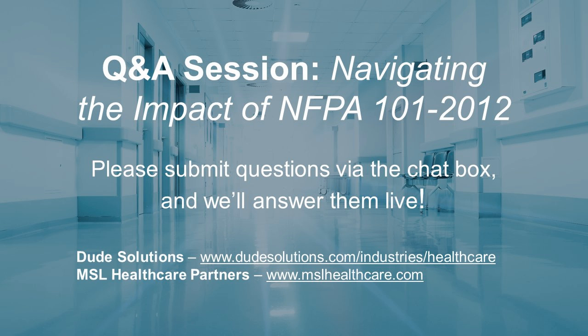Good question. If I would have answered before I got this CMS K-tag document, I would have said yes, I would certainly recommend that they be that. But based on what CMS is saying in this K-tag document, they simply have to be UL listed. There's no requirement that they be hospital grade.